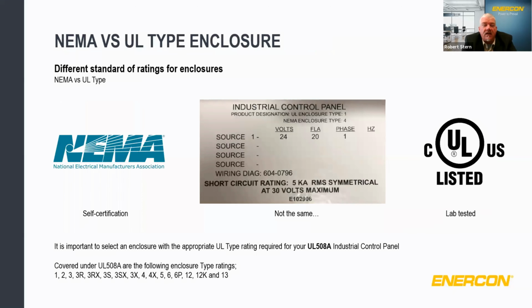A common misnomer regarding NEMA classification and UL type ratings: they are not the same. While they have similar definitions, the NEMA class, such as NEMA 4, is determined by a self-certification process by the enclosure manufacturer. The type rating under UL is conducted by an approved test lab under the UL 50 or UL 50E standard to determine whether or not that enclosure can withstand to varying degrees those elements, whether it's direct water pressure, rain, sleet, ice, etc. So, for example, a NEMA 4 product and a UL Type 4 could be considered similar in their ability to withstand weather. However, the UL type rating is what applies.